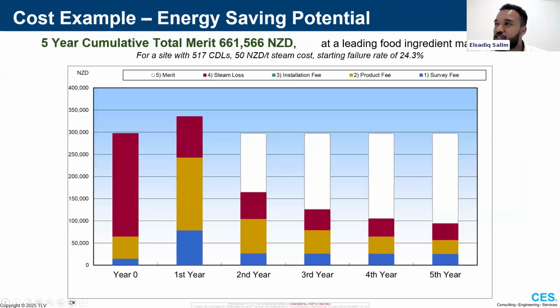To talk about the costs now, this is another site, a leading food ingredient manufacturer in New Zealand. This is a simulation we put together based off the data we've collected globally on the typical trend for steam trap management. You can see the red bar on the left-hand side at year 0. That's their steam trap leakage losses today. And the other two bars, the blue and, I'm a bit colorblind, green, orange, the other color in the middle there, that's what they're paying now for steam trap replacements and for steam trap surveys.